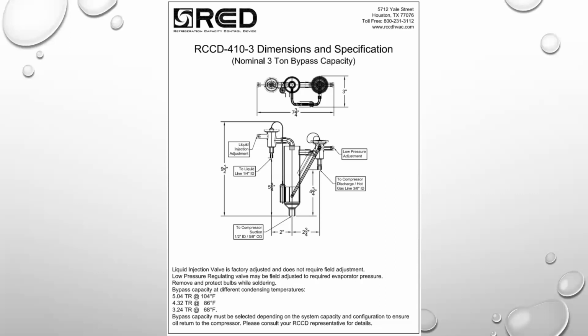Also, you'll see that there are 2 bulbs. The valves look identical. They're not identical. The TXV, the liquid injection adjustment, you will not touch it. That remains as it is. You don't bother. You don't touch it at all. The hot gas, all adjustments are done on the valve that enters the side of the unit.